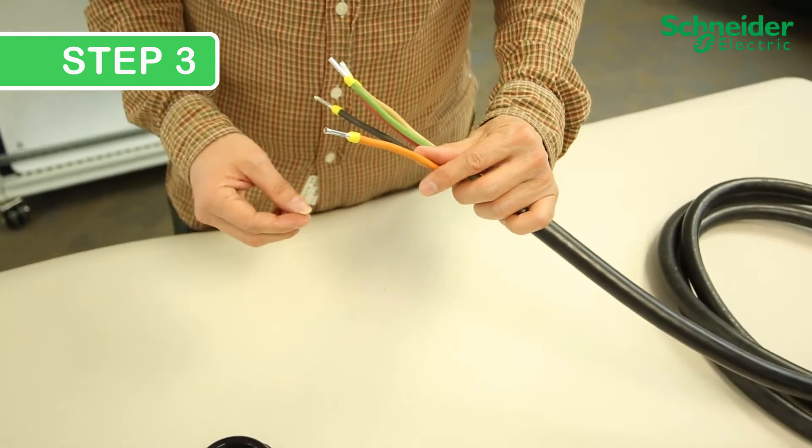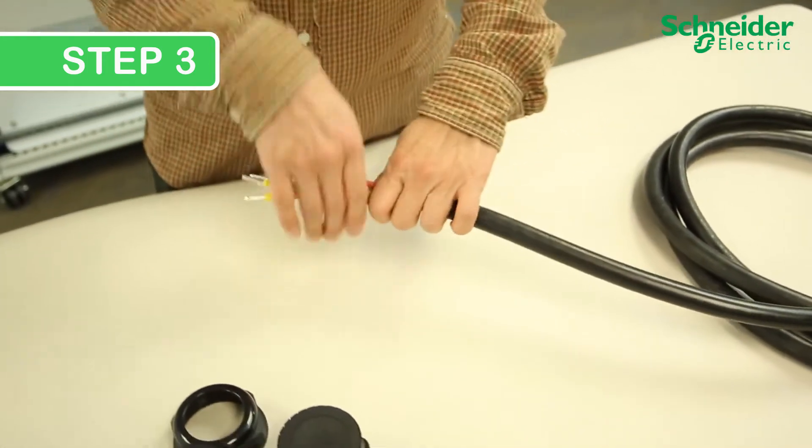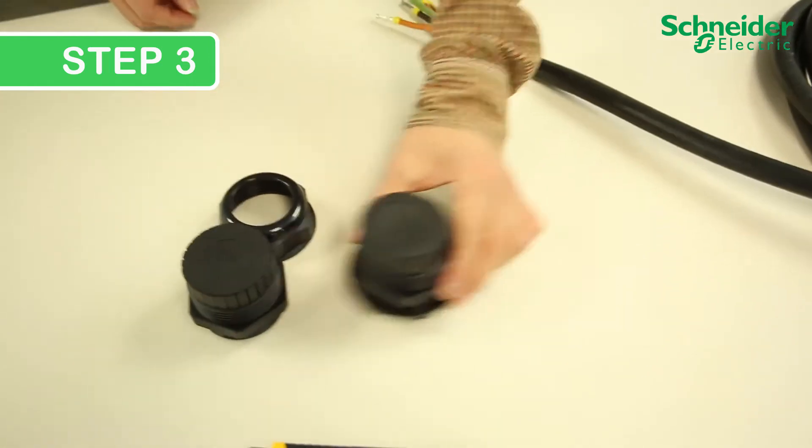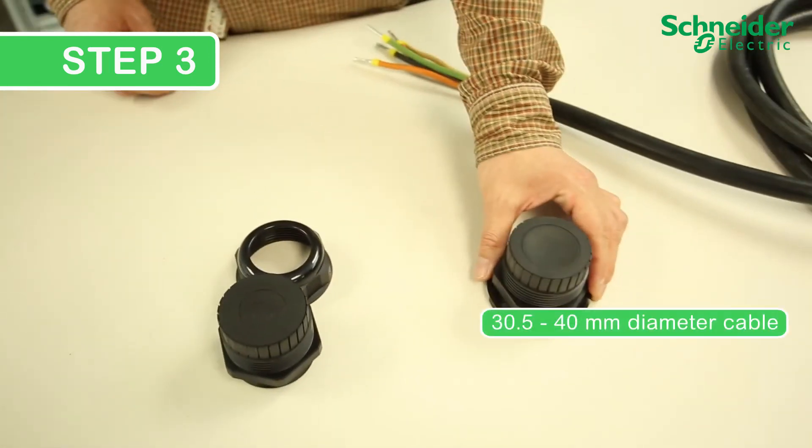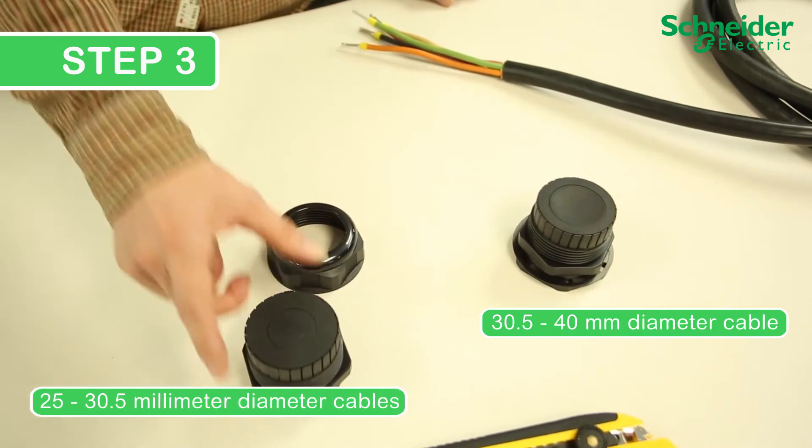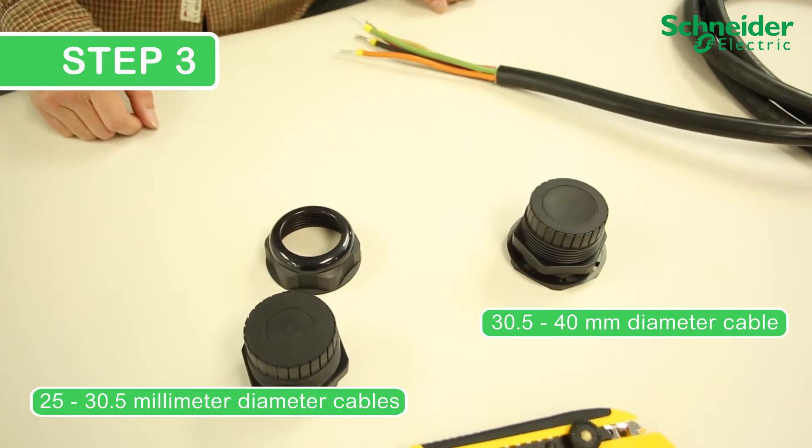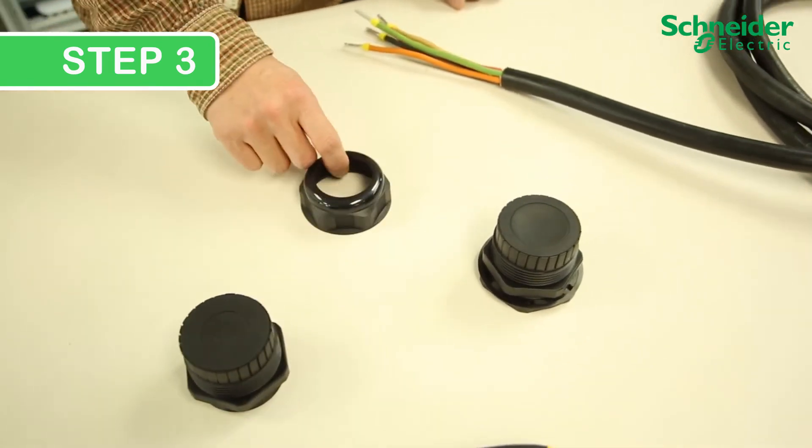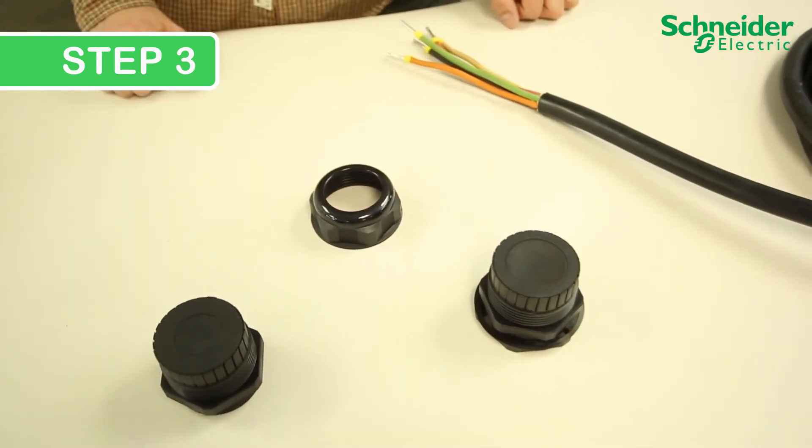With the CL60 comes two AC glands. One is pre-installed for 30.5 to 40mm diameter cables. And a second size is included with the accessories for smaller 25 to 30.5mm cables. A single sealing ring to clinch the gland is included as well. It is to be used with both AC glands.